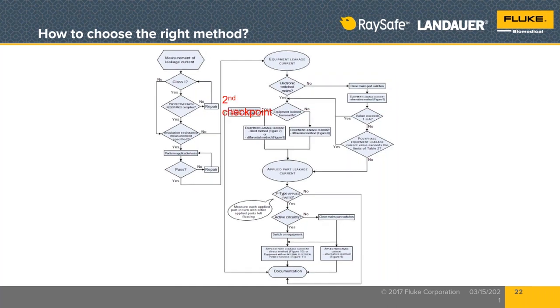Second checkpoint: is the device under test isolated from protective earth or ground? Now, in some countries, the language doesn't have a separate word for isolated or insulated, but I need you to understand they are two very different things. Isolation means that there is a barrier of some kind where the electrical current flowing inside the medical device is not referenced to ground. It is referenced to something other than protective earth. And that's done to protect the patient from electrical short circuits and so forth, or high energy that might come in through the ECG electrodes.